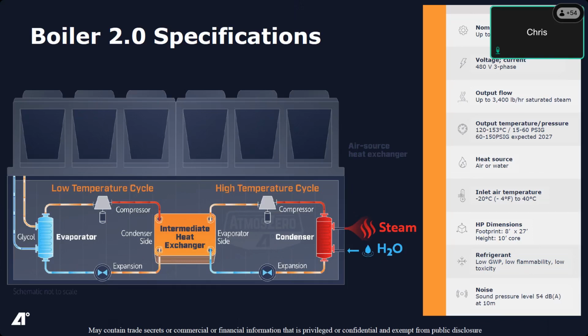The left side of the double heat pump thing you see there is the evaporator. One thing very specific to AtmosZero is you will see that glycol loop that goes into the air coil. The glycol loop is some of the magic bullet and IP that we have in the company, in the sense that we can keep the refrigeration or the vapor compression loops the exact same for every single different facility because of that glycol loop. What we're doing is we're varying the flow to match the heat rate of that evaporator to keep the compressors of the heat pumps where they need to be on their operating curves. And so whether you have a heat source that is 20 degrees Fahrenheit or 80 degrees Fahrenheit, that glycol is what allows that flexibility into a facility.